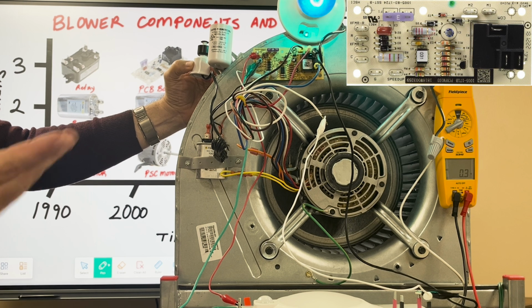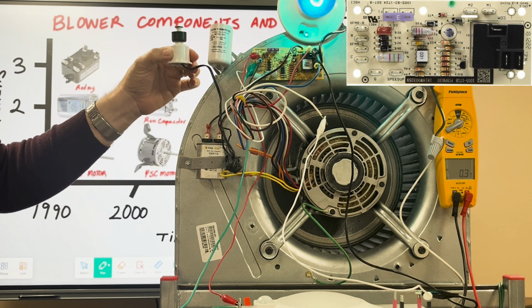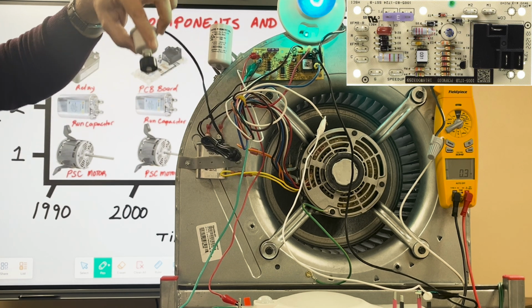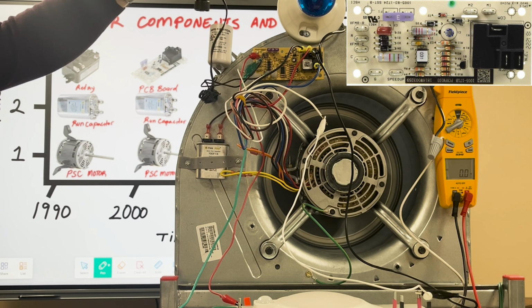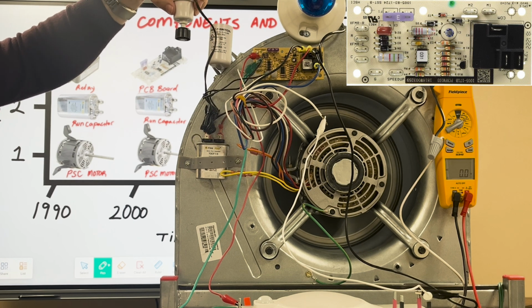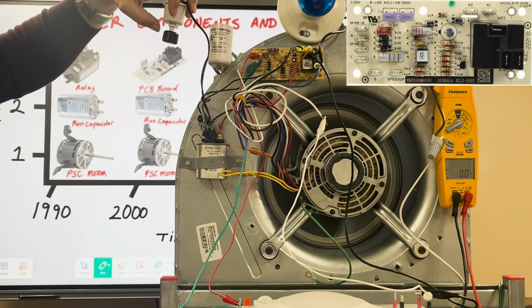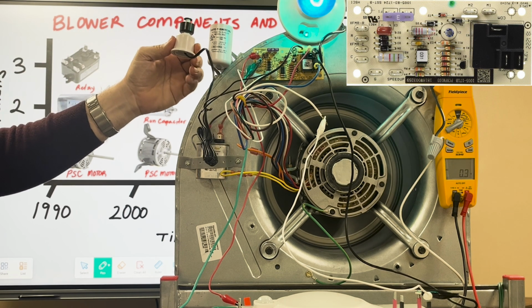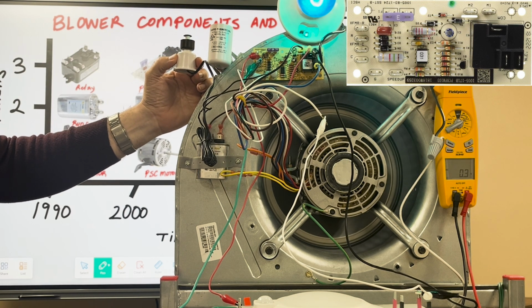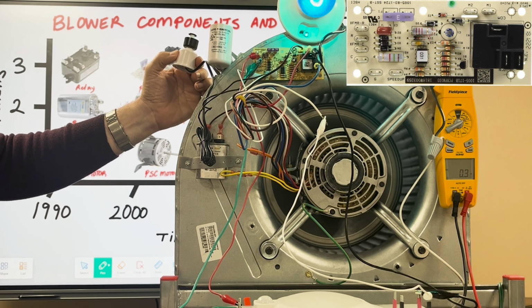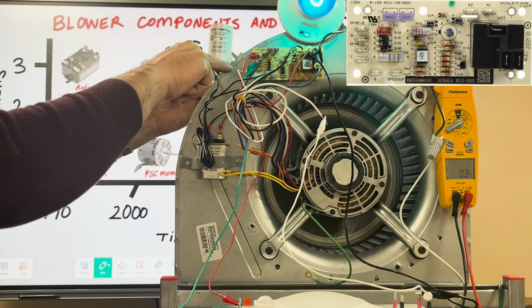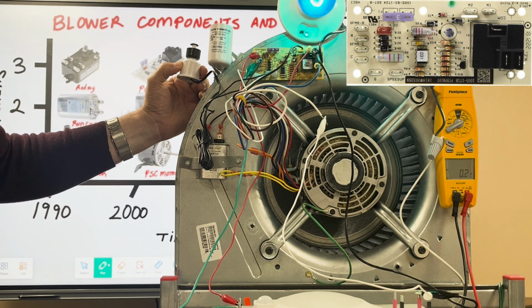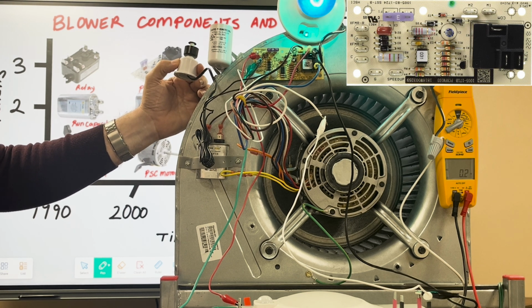And so now, say I cleared out my drain line and it's good to go. There is no delay. It's immediately on. And when I lose that G call, it's immediately off. And so if you had a situation where you didn't want that delay, you just wanted that blower to turn right off when the compressor shuts down, then you just simply short out between G and speed up, and there will be no delay.